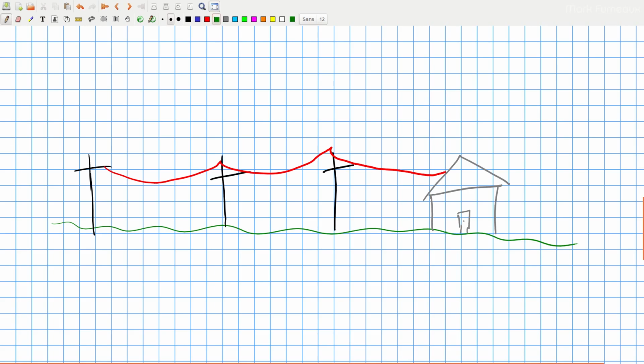What they do is use the ground as the return path. There's a stake that goes into the ground on this end, and over near civilization there's another stake that goes into the ground. The circuit is pretty much this: they pass current through the live, and it returns through the earth, and then the next half of the cycle that reverses. The losses are ridiculously high because copper is a very good conductor of electricity, and earth is not. But it can be cheaper for them to lose the electricity through the ground than to install two sets of wires. It's just how cost-benefit analyses turn out. But it is possible to complete a circuit with the earth—it's just not recommended.